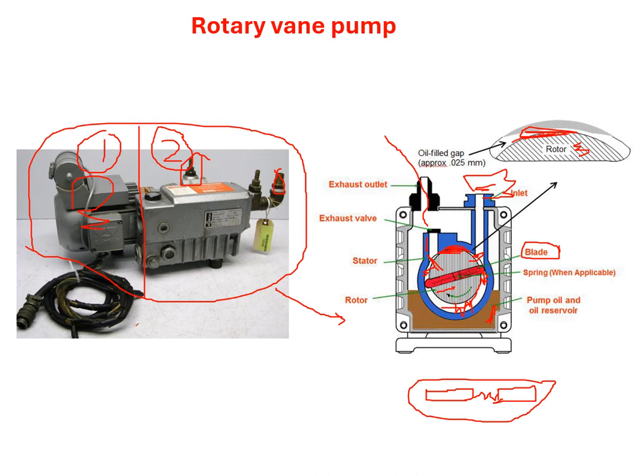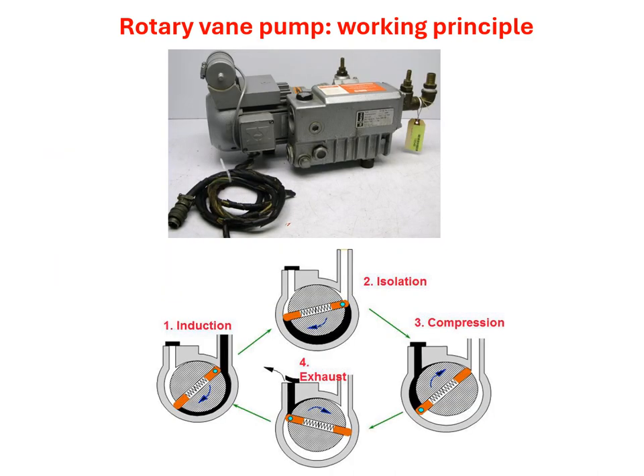Now let's see how this pump actually creates the vacuum. This is done in multiple stages — here you can see four stages. The first stage is induction: the inlet is connected to the chamber and all the gases come through this inlet inside the pump. As the blade moves, these gases also move inside. The second stage is isolation: the blade is now in a position where the gases that came inside are separated from the inlet.